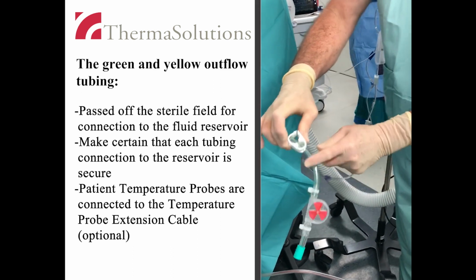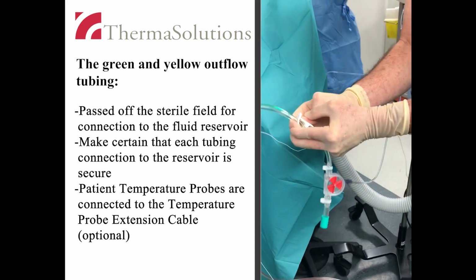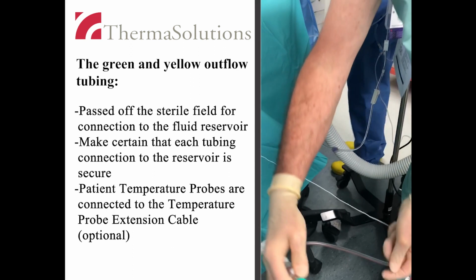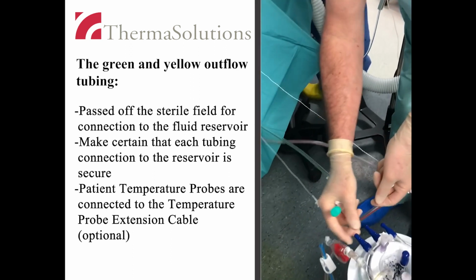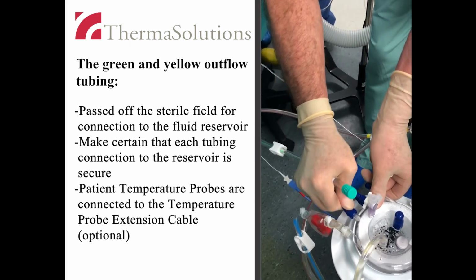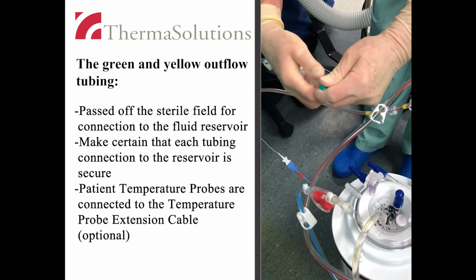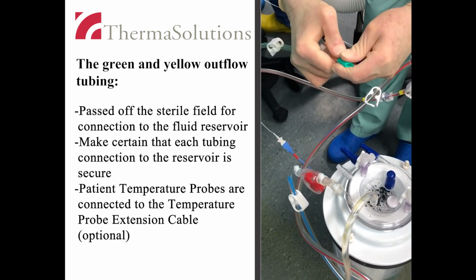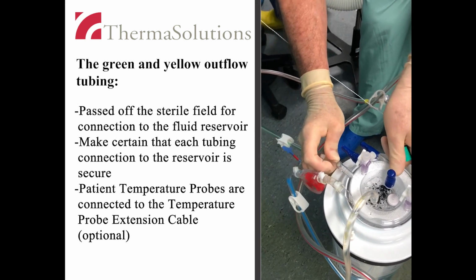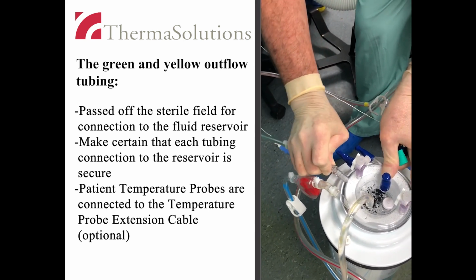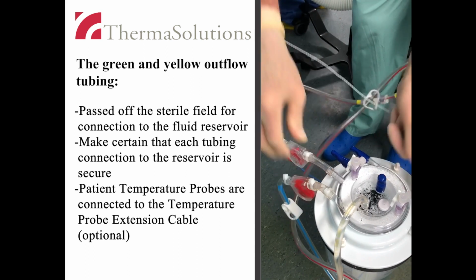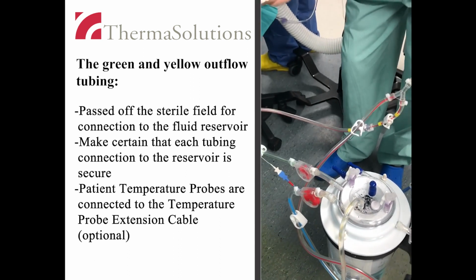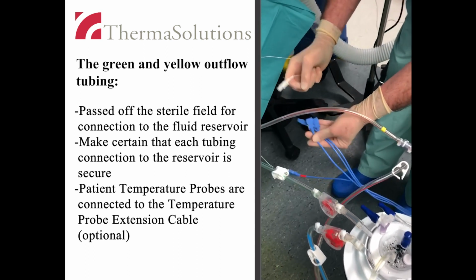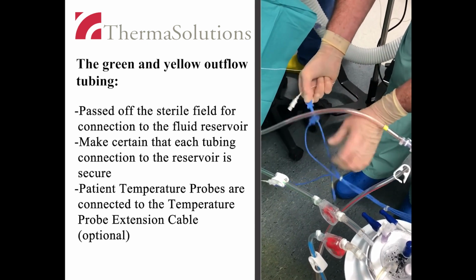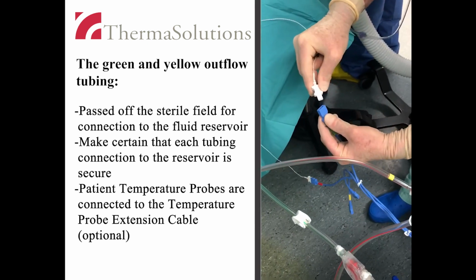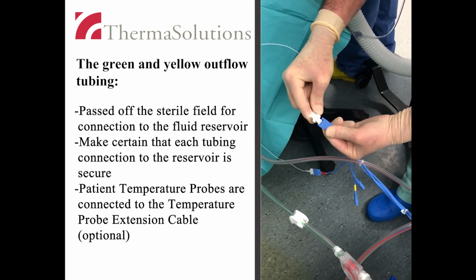The green and yellow outflow tubings are passed off the sterile field for connection to the fluid reservoir. Make certain that each tubing connection to the reservoir is secure. The patient temperature probes are connected to the temperature probe extension cables. While not necessary, these temp probes on the blue, yellow, and green tubing can be connected via the extension cables to the corresponding color on the connector panel.